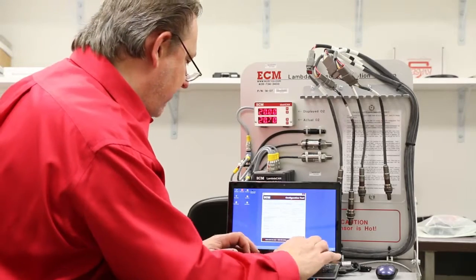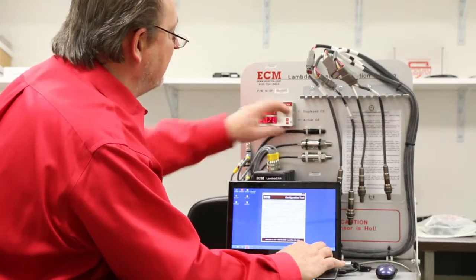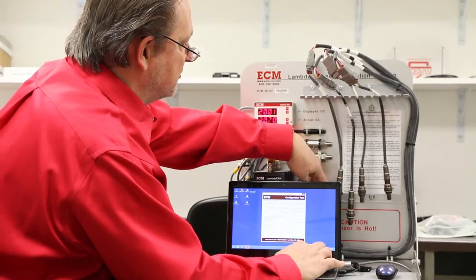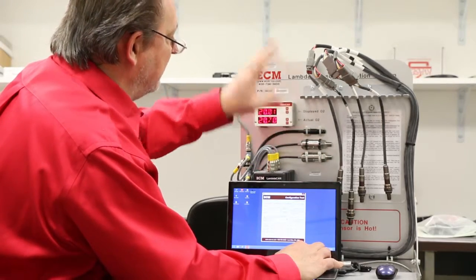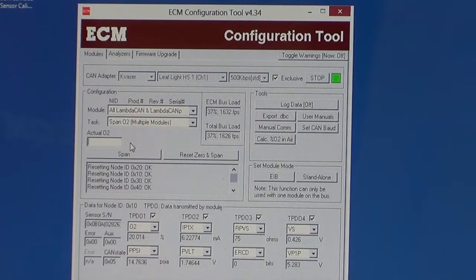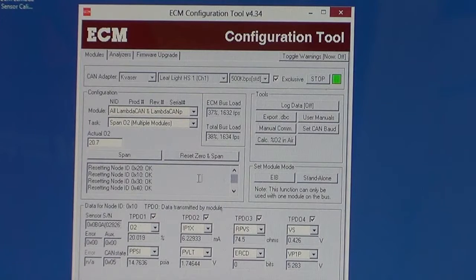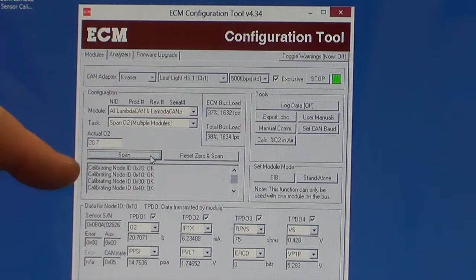So you type in 20.7, it should be moving around, and hopefully the smoke from these sensors isn't confusing this thing. Everything should be nicely cleaned out. And you put 20.7 in there, and then you click span. This is going to take 10 seconds of data, and it'll do its countdown, and after, it's going to say calibrating node ID for 20, 10, 30, 40. If everything's okay, it'll say okay.